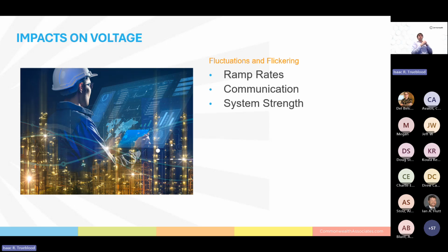What can we do to mitigate this fluctuation? One way is to limit the time it takes for distributed energy resources to increase and decrease generation. It's also known as a generation's ramp rate. For predictable distributed energy resources like batteries or fossil fuels, this is often less a concern as ramp rates can be predicted and controlled. However, wind and solar, while often predictable, can on occasions be unpredictable. Sudden increase or decrease in sun or wind can make a site suddenly change how much power it can generate.